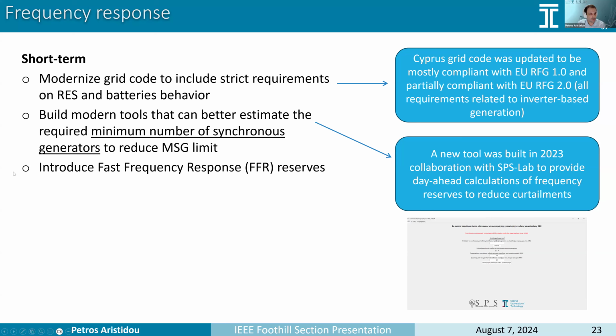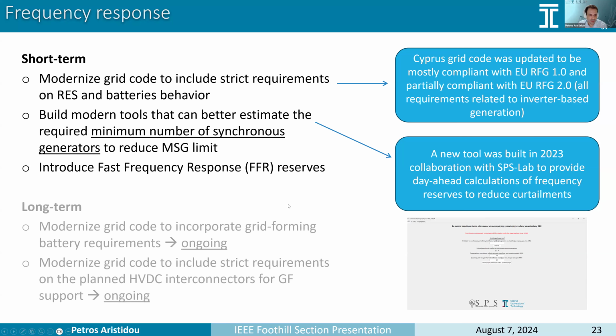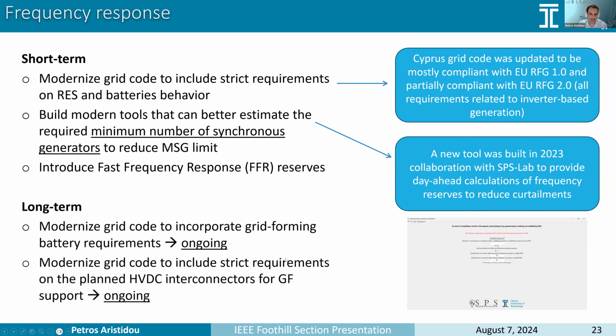which translates to a lower minimum stable generation limit, which translates to fewer disconnections. And the other point is to introduce fast frequency response reserves. In the long term, there is a push to move into grid forming, modernize the grid code to incorporate grid forming battery requirements, and they're also looking into HVDC interconnections to different countries in order to provide more support and try to stop this renewable energy source curtailment.